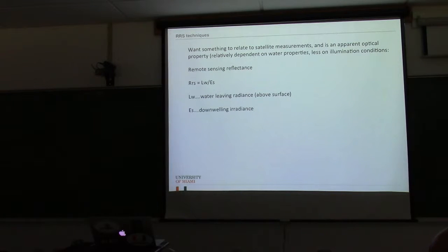What you'd really like to have is some source you could look at that's stable, that you get the calibration back from the manufacturer, and in your lab you're using that as a stability check as you're going along. For the most part, that's probably the best thing you could do.